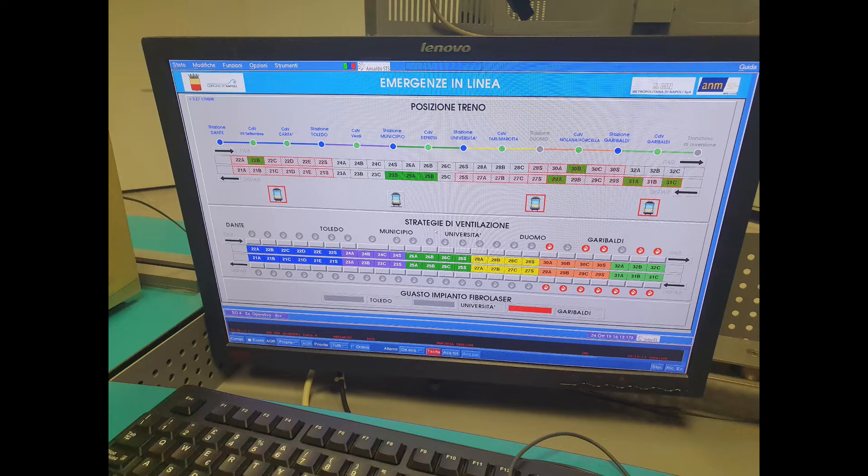The emergency management monitor identifies various reference points of the metro such as stations and ventilation chambers (CDV). A dedicated monitor handles ventilation strategies for the new section from Dante to Garibaldi. Even-numbered reference points (22, 24, 26) indicate the Garibaldi section, while odd-numbered points (21, 23, 25) indicate the Piscinola direction. The monitor also localizes train positions and ventilation strategies for absolute emergencies like a tunnel fault or fire.